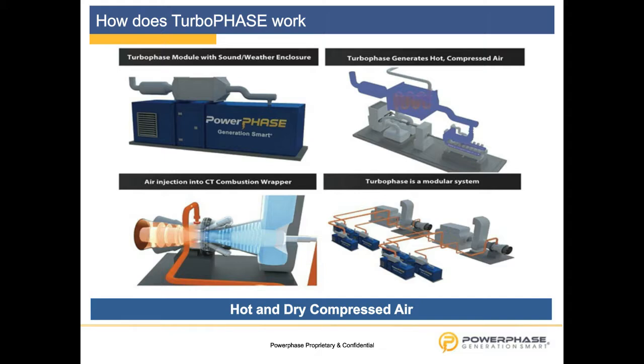Then I go to the lower left picture, in which we see that the compressed, heated and dry air is injected into the compressor discharge plenum, bypassing the compressor actually. And on the right lower picture, you see a benefit: it is a scalable modular system. In this very case, there are 6 Turbophase modules connected via a common header to 2 gas turbines, allowing maximum flexibility in terms of operation, in terms of maintenance, and so on.